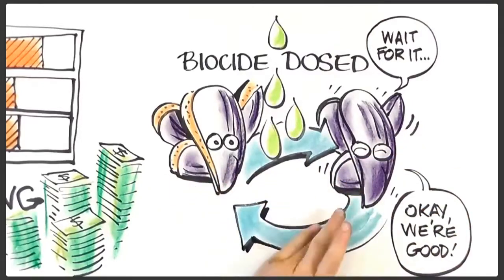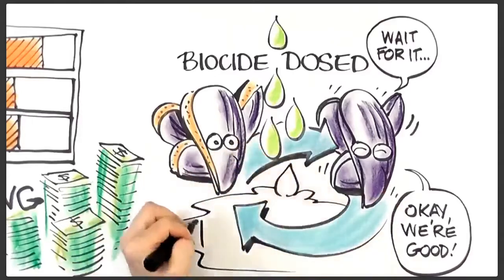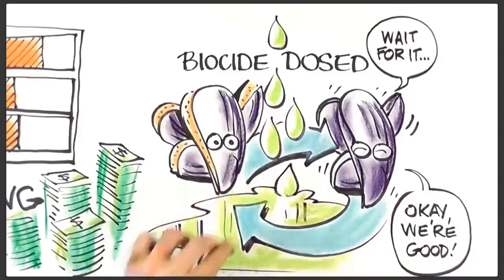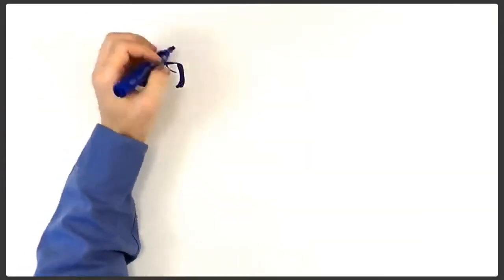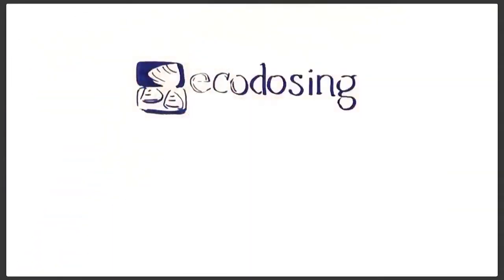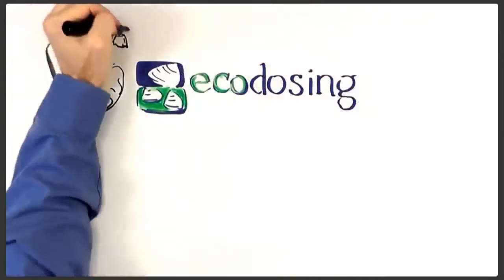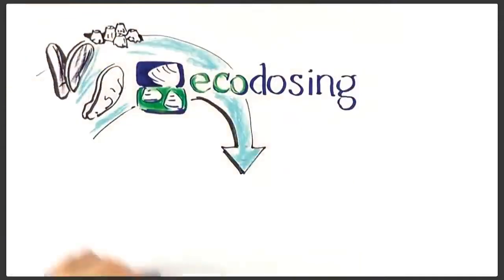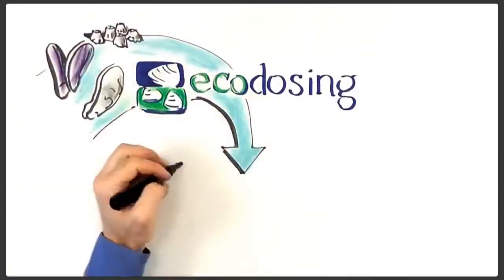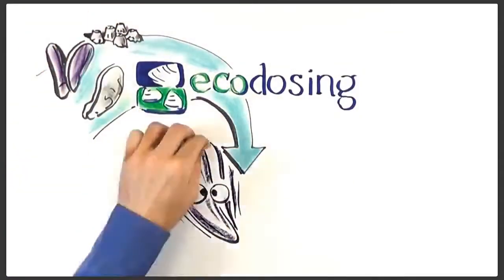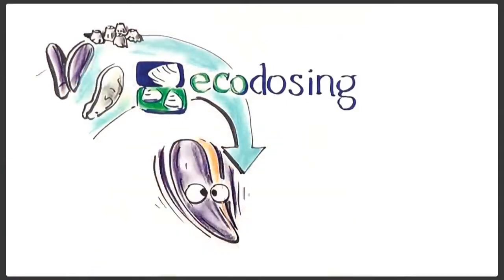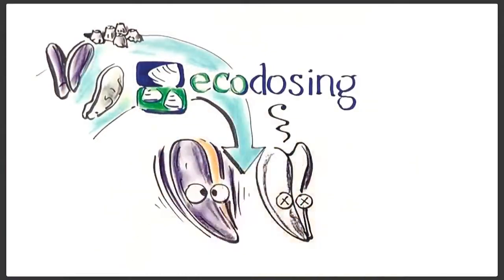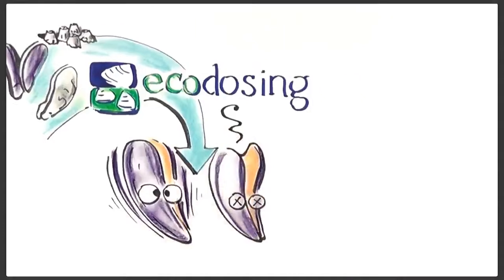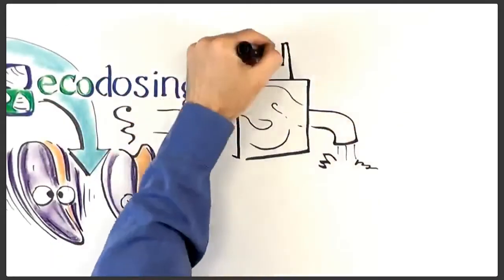However, continuous application of biocide has a hefty environmental impact. It's also very costly since most of the biocide is wasted. Ecodosing is different: to calculate the optimal required dosage, it analyzes the natural response of organisms to biocides. The Ecodosing method forces the animals to become highly active, exhausting them and allowing the biocide to work. This allows biofouling to be cleared from the cooling system more quickly and efficiently.